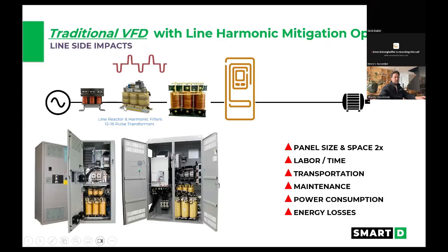So on the line side, the traditional ways of mitigating these things is we'll put in, again, a good, better, best solution. We'll either go with a line reactor, passive harmonic filter, or an active harmonic filter. And then we have to put them all into a cabinet. And you see these cabinets here, they're pretty gigantic. This is just the VFD here. But now we have to make a cabinet large enough to house everything. And so you end up with these 6 and 8 foot cabinets and so on. So that increases your costs for sizing, increases labor, of course, transporting them from manufacturing to site, etc., maintenance, power consumption, and energy losses. So it gets rather cumbersome.